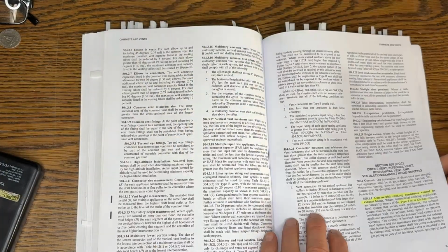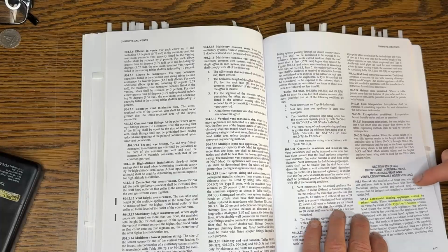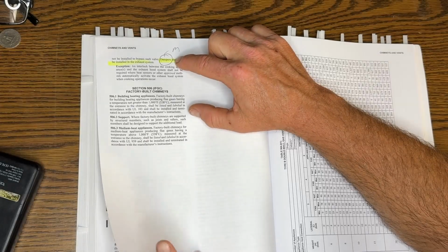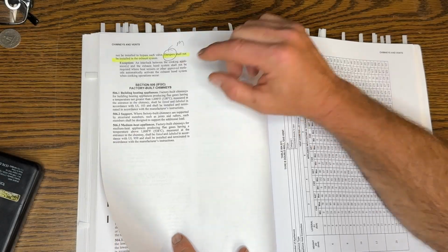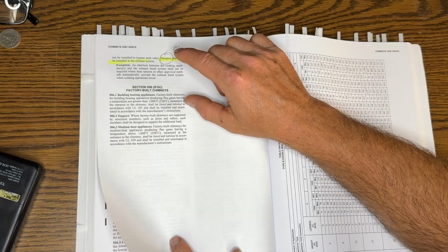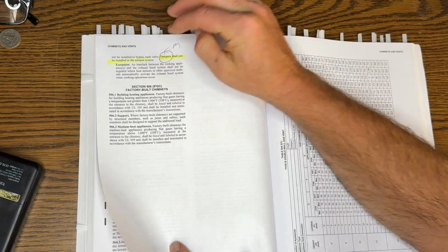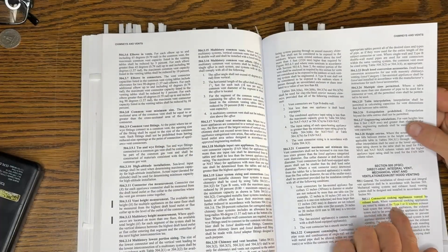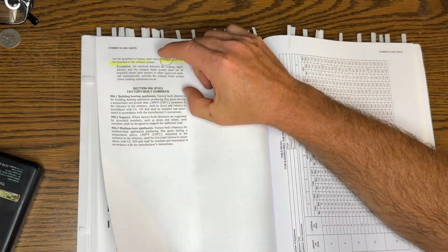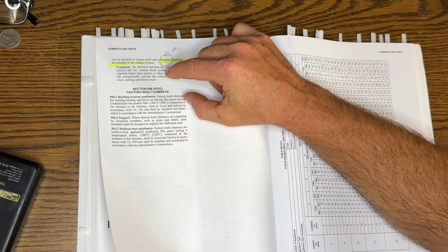I had multiple questions on dampers, not just one. So dampers come up anytime they say that it's a mechanical damper that you can set. It's a thou shalt not. But look at this. Look at the exemption. It's an interlock. You can have a damper in a vent, in a commercial cooking appliance vent, only if it's interlocked between the cooking appliance and the exhaust system.